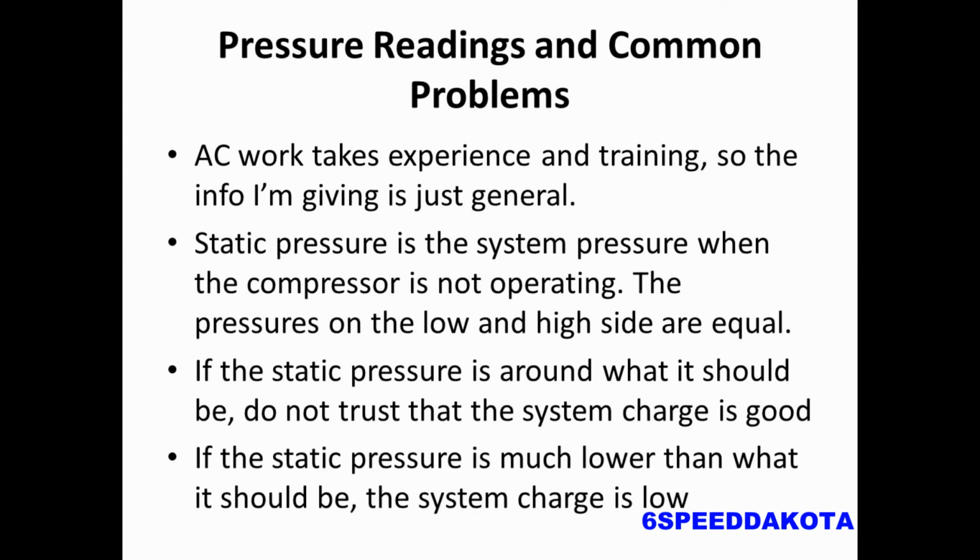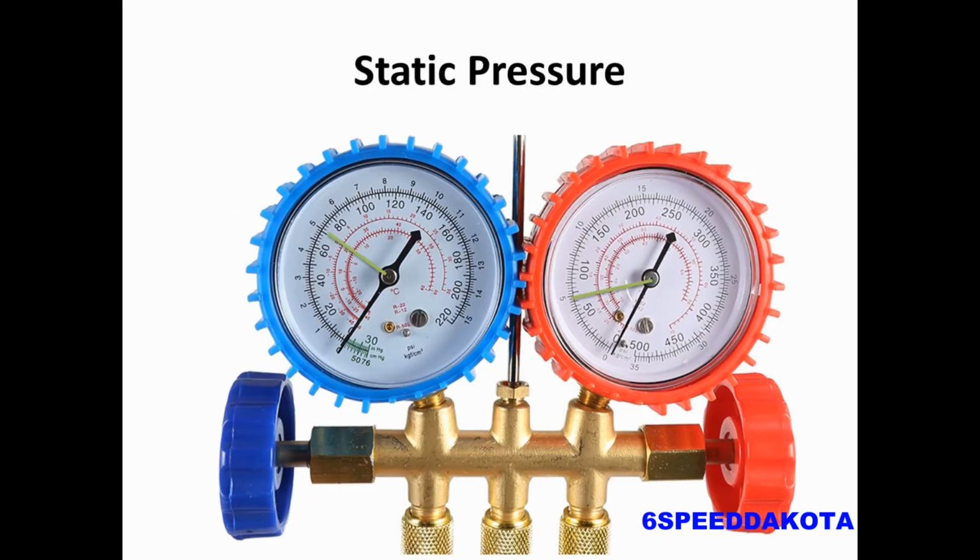If the static pressure is a lot lower than what it should be, then we can safely assume that the system charge is low. So we're going to go from approximately 70 degrees Fahrenheit for our static pressures.